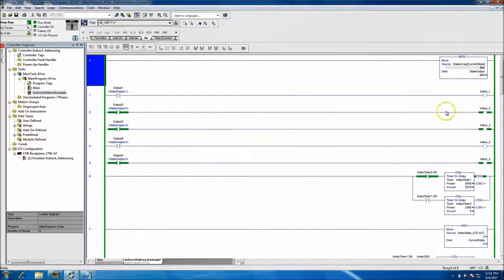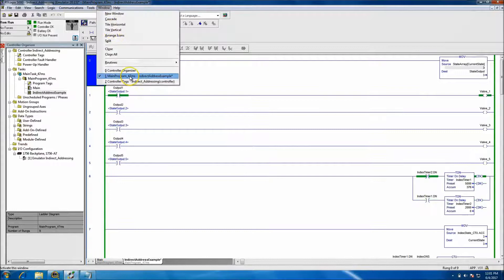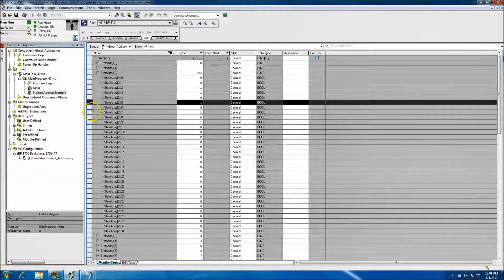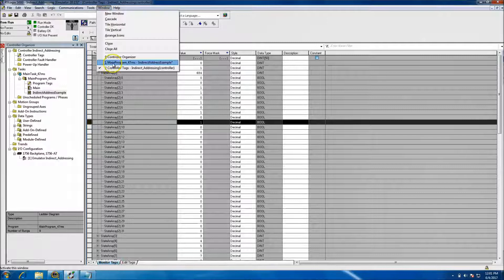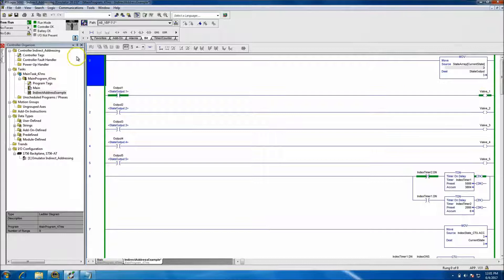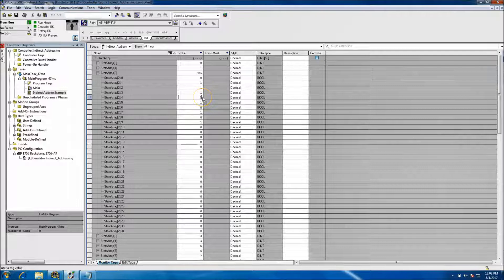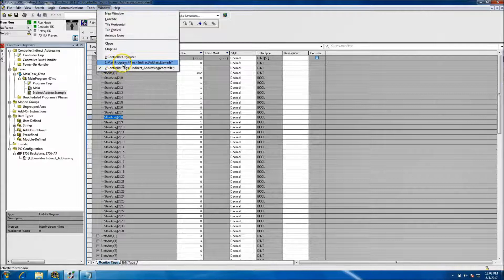In state 2, or where our indirect address is 2, we have these bits being set: bit 2, bit 3, bit 5, bit 7, and bit 9. So when it hits state 2 it's going to cut on valves 2, 3, and 5. When it's at state 3 it's only going to cut on one. Let's change that — say we want to cut on 1, 2, 3, and 4. Okay, so in state 2 it cuts on all the valves now.